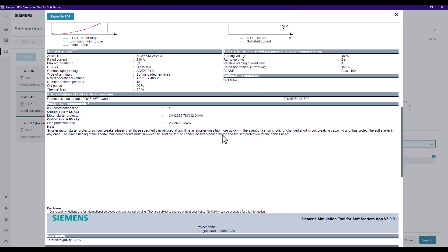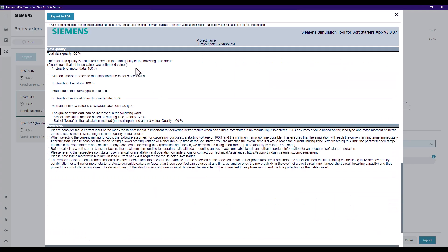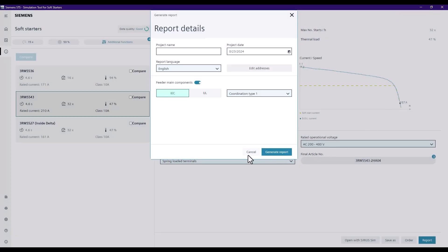Most importantly, the report gives you recommended parameters for the initial commissioning, making that process much easier. It also provides the feeder main components — options for an MCCB or fuses for line protection, and the frame size of the optional line contactor. On the last page, the Data Quality Advisor shows what it's been tracking throughout the simulation and points out areas where you haven't achieved 100% accuracy, which is important if you encounter problems at commissioning and need to refer back to this document.